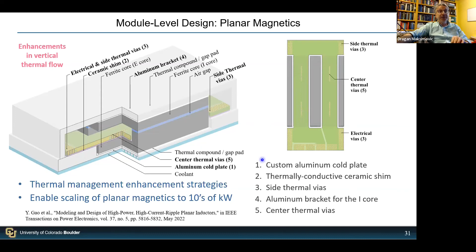That was the main motivation behind looking into planar implementation of the magnetics. Thermal management enhancement strategies were applied to make it possible to have those planar magnetics applied at tens of kilowatts level. Those strategies include a custom aluminum cold plate, a thermally conductive ceramic shim between the core and the cold plate, thermal vias embedded into the winding, an aluminum bracket placed on top of the I-core of the magnetic, and uniquely, inside the winding we have thermal vias, because these internal points within the PCB winding are where we actually see the highest temperature rise.